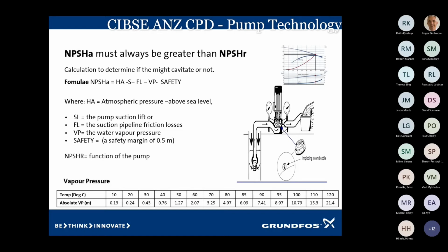If we look at that calculation as to whether or not a pump will pull water from below the ground, and this is an application where we're pulling cold water, we're pulling water from a stream and we want to pump it out. We must make sure that atmospheric pressure, which is the net positive suction head available, is always greater than the net positive suction head required.